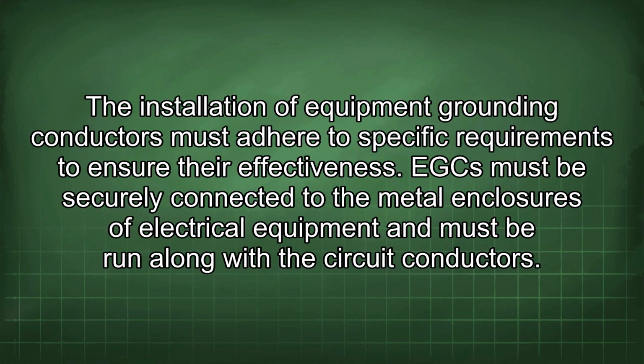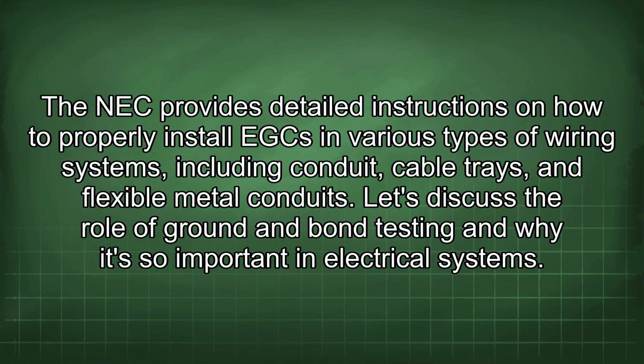The installation of equipment grounding conductors must adhere to specific requirements to ensure their effectiveness. EGC must be securely connected to the metal enclosures of electrical equipment and must be run along with the circuit conductors. The NEC provides detailed instructions on how to properly install EGC in various types of wiring systems, including conduit, cable trays, and flexible metal conduits.